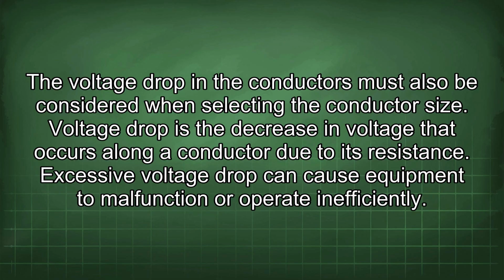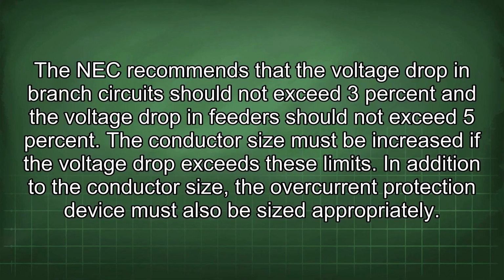The voltage drop in the conductors must also be considered when selecting the conductor size. Voltage drop is a decrease in voltage that occurs along a conductor due to its resistance. Excessive voltage drop can cause equipment to malfunction or operate inefficiently. The NEC recommends that the voltage drop in branch circuits should not exceed 3% and the voltage drop in feeders should not exceed 5%. The conductor size must be increased if the voltage drop exceeds these limits.